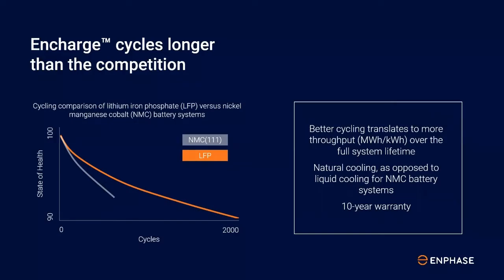When it comes to the energy capacity of a battery, what are you really paying for? It's not the capacity on day one, it's the amount of energy you can put into and pull out of the battery over the 10+ year life expectancy. All batteries degrade in terms of their capacity with regular use. LFP chemistry, which we use in our Encharge batteries, degrades at only about half the rate of NMC, the chemistry of Powerwall and LG Chem. So over the lifespan of the battery, you're going to get a lot more throughput of energy with an LFP battery. This graph shows us that after 2,000 cycles, the LFP battery will still have about 90% of its original capacity. By comparison, NMC batteries degrade to 90% after only about half that number of cycles.